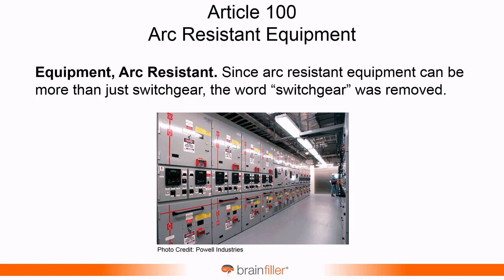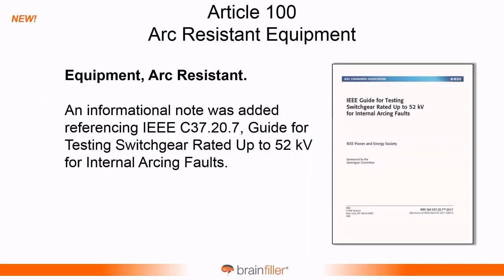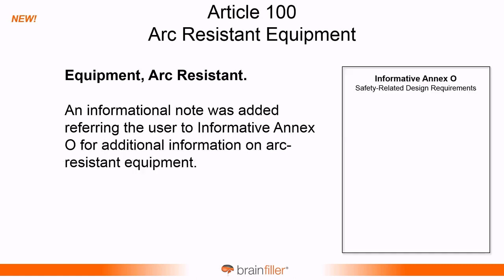We also have the term arc-resistant switchgear being changed to arc-resistant equipment. And the reason for this, when this type of construction was first introduced years ago, it was switchgear. But over the years, there's been the introduction of arc-resistant motor control centers and other types of equipment. So it's time to move the focus away from just being switchgear and move it towards arc-resistant equipment. And there was an informational note that was added this time around referencing the appropriate standard, IEEE C37.20.7, which is the guide for testing switchgear for internal arcing faults. And also, there's a reference to Annex O, which is for safety-related design requirements.